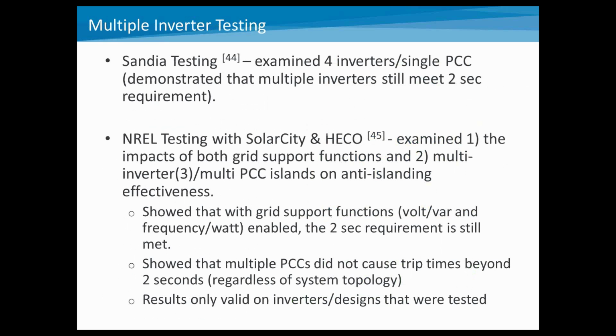If we go on to additional things, one of the questions that often comes up is, what about multiple inverters? Obviously, singular DG installations are getting rarer now, and we're starting to see many more multiples of inverters. Both Sandia and NREL have done a variety of tests in this space. Sandia, if you see the reference there, examined four inverters at a single point of common coupling and demonstrated that multiple inverters still met the two-second requirement that's in the standard.